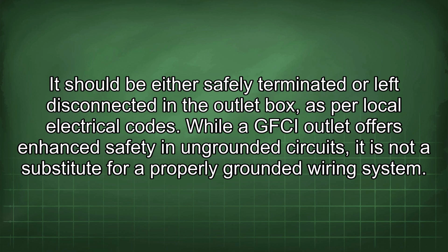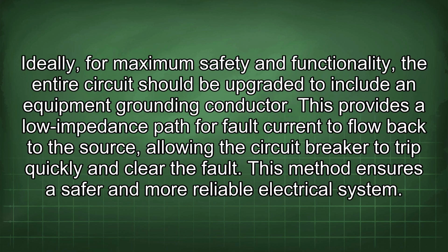electrical codes. While a GFCI outlet offers enhanced safety in ungrounded circuits, it is not a substitute for a properly grounded wiring system. Ideally, for maximum safety and functionality, the entire circuit should be upgraded to include an equipment grounding conductor. This provides a low impedance path for fault current to flow back to the source, allowing the circuit breaker to trip quickly and clear the fault. This method ensures a safer and more reliable electrical system.